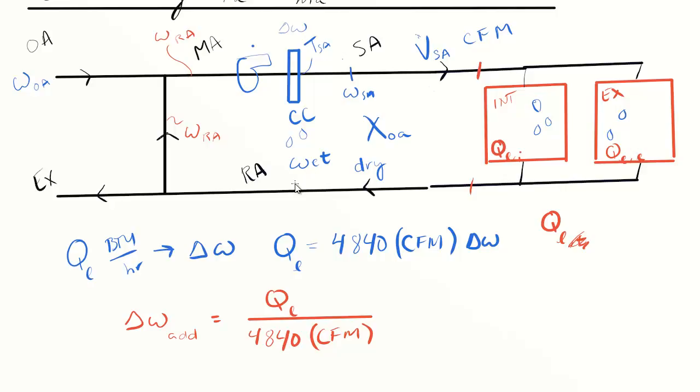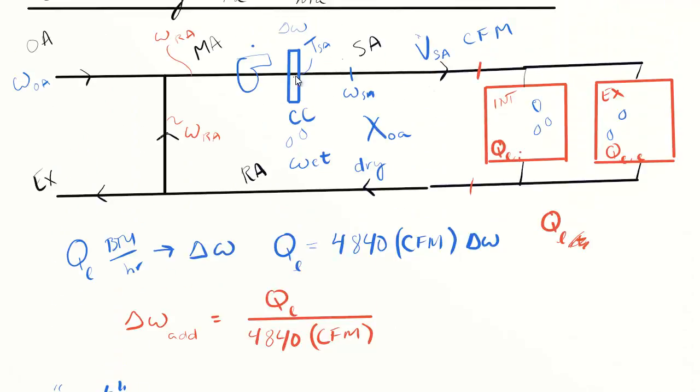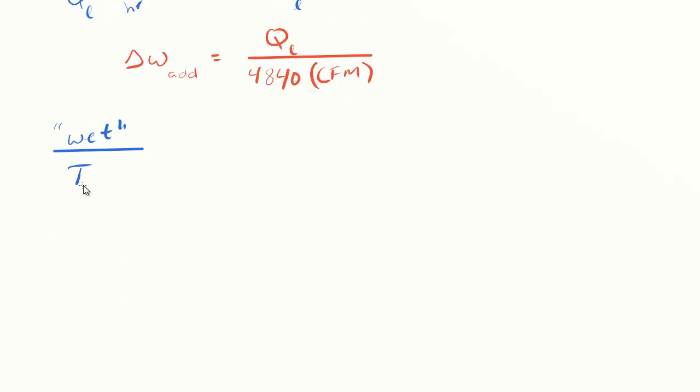Let's begin by assuming the wet case. If the cooling coil is wet, one nice thing we know is that this air coming off the coil is saturated or near saturation. A good assumption is that it's at 90% relative humidity coming off the coil. If you know psychrometrics, having a temperature and relative humidity can lead you to an omega value.